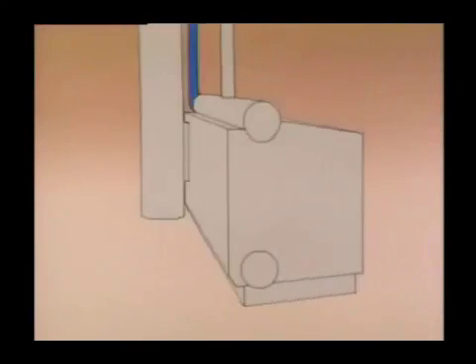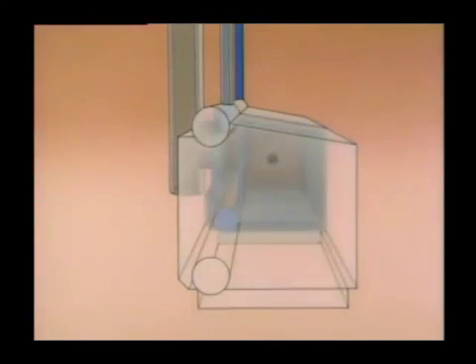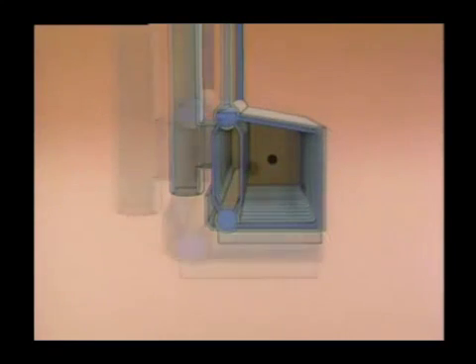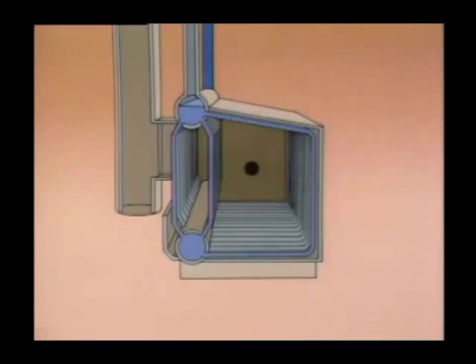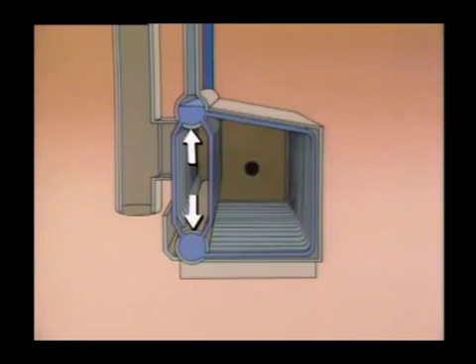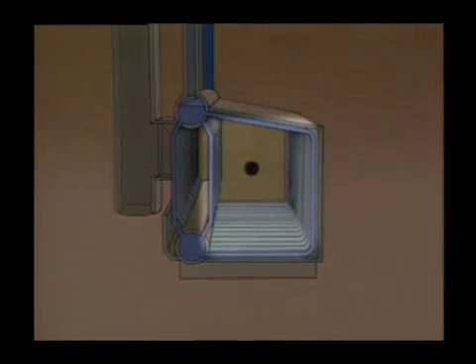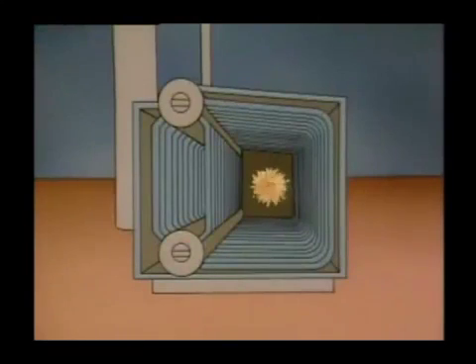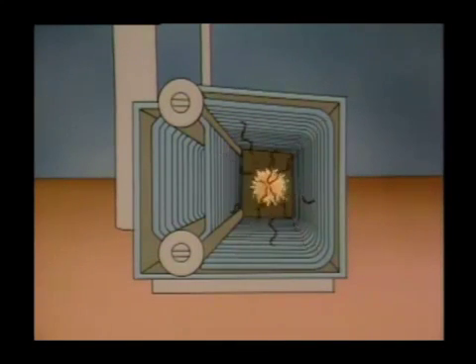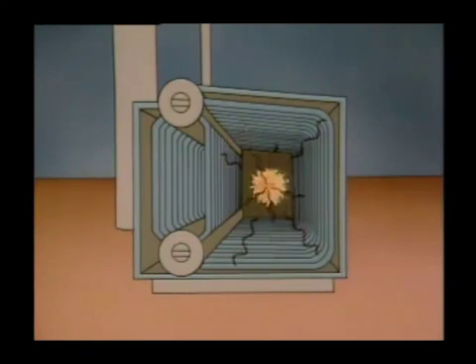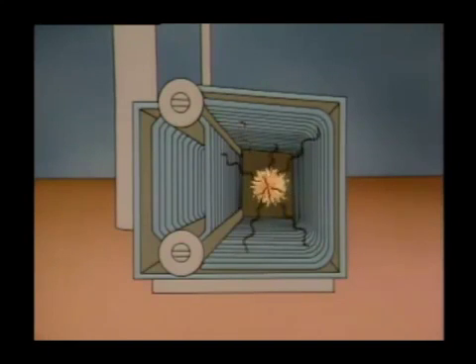To see how, we'll use a water tube boiler as an example. The heat transfer principles at work apply to just about all boilers. The boiler has a series of tubes and two drums that distribute water to the tubes. The tubes form a wall around the combustion area, where heat is generated. When fuel burns, radiant energy in the form of electromagnetic waves is produced. These waves travel through the combustion area, and those in a direct line of sight with the tubes make contact with the outer tube surfaces — the tubes absorb heat. This is radiant heat transfer.